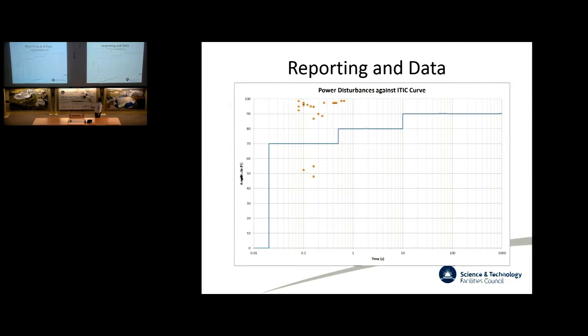by 0% for 20 milliseconds, and then obviously 70% for the next just short of a second, and then should be able to cope with an 80% drop for up to 10 seconds and a 90% drop continuously. All of our devices do conform to this. However, you can see here that there were 3 little dropouts, which actually caused interruption to the experiment. Instead of chasing our tails, wondering why various pieces of equipment had stopped, we were able to go to this graph and say, oh, look, there's 3 occasions here where we lost the mains voltage, and attribute the faults to those.